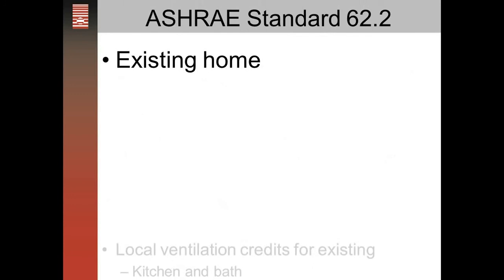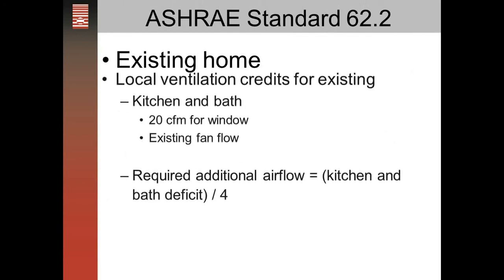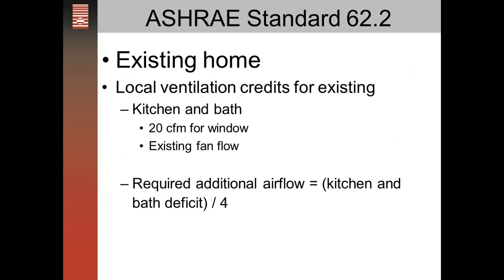For an existing home, you can take credit for existing fans you have for local spot ventilation. For a kitchen or a bathroom, if you have an operable window you can take a 20 CFM credit. If you measure the existing fan flow, you can take credit for that also.